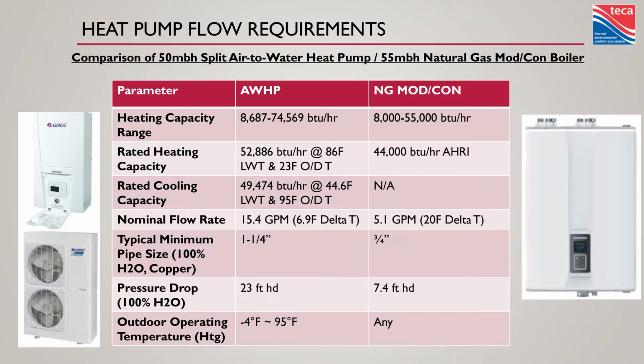So if you were sizing that for a 20 degree delta T with 100% water, that could be a 3/4 copper pipe. The other one's going to need 1.25 inch minimum. Those are minimum sizes. We haven't even started adding glycol or distance. So that right there is the first step in properly applying these products. Let's take a look at pressure drop.